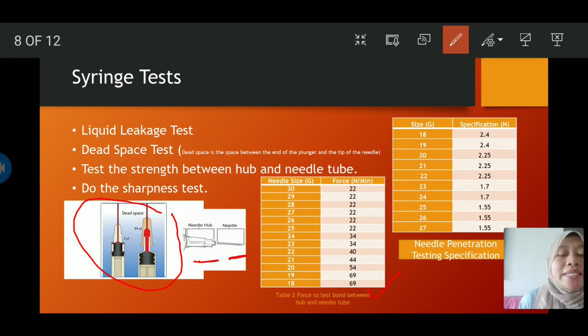And then the fourth test is the sharpness test. This table shows the specification of the sharpness test. We inject the needle into 3mm rubber. This rubber is like our skin, so if the value shown on the meter is less than the specification value, it means the needle is sharp enough to be used on the patient, so that the patient won't feel any pain during the injection process.